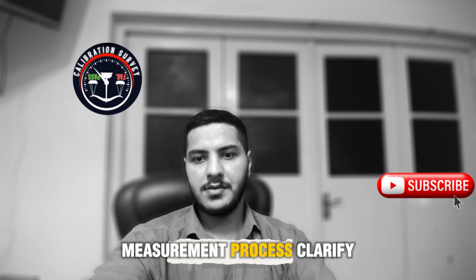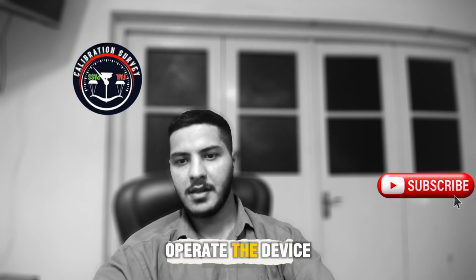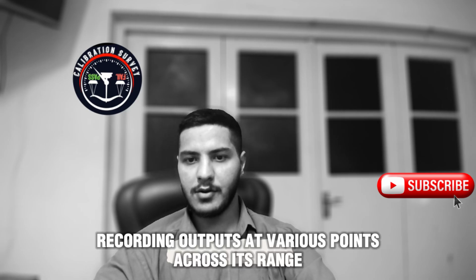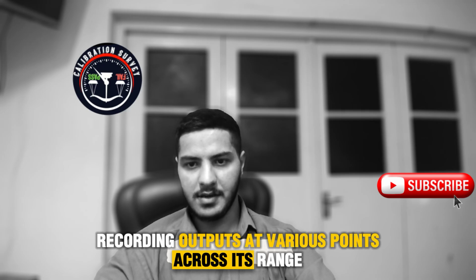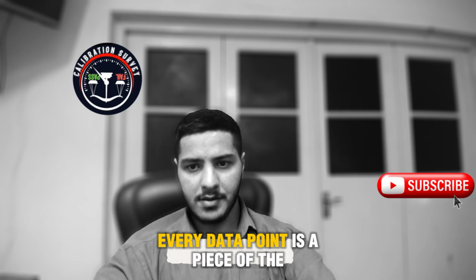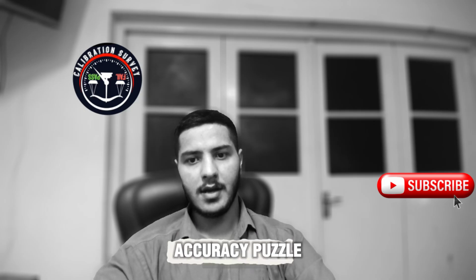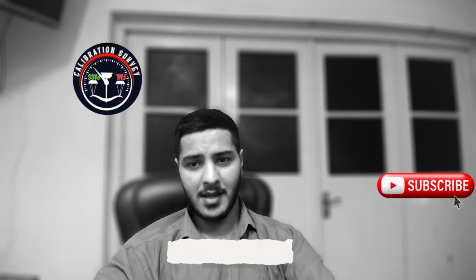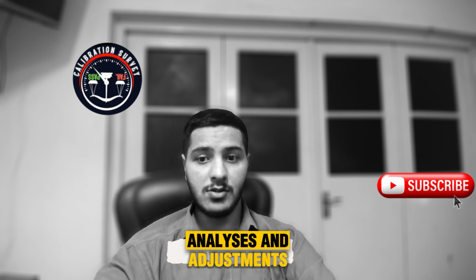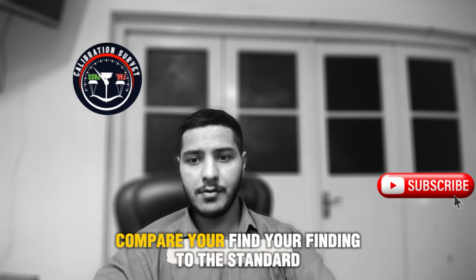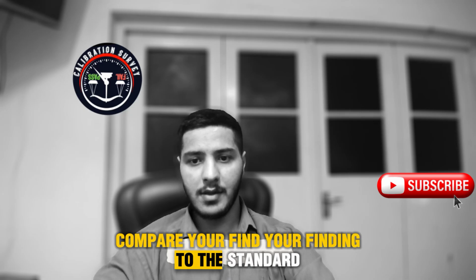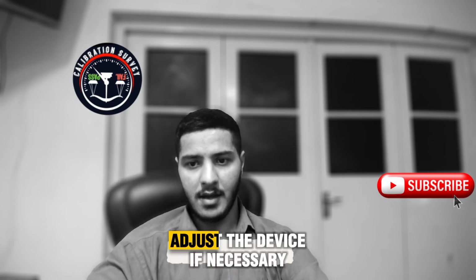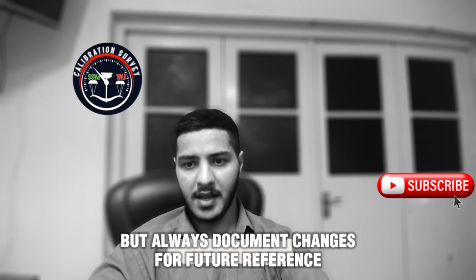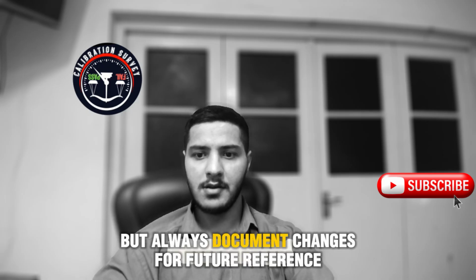Measurement process. Operate the device, recording outputs at various points across its range. Every data point is a piece of the accuracy puzzle. Analysis and adjustments. Compare your findings to the standard. Adjust the device if necessary, but always document changes for future reference.